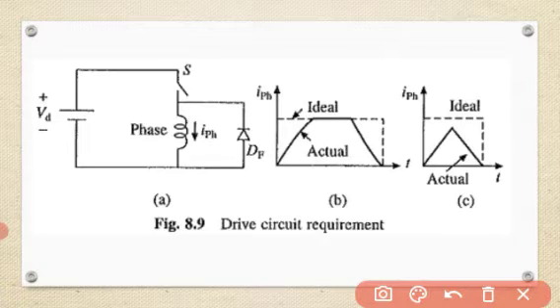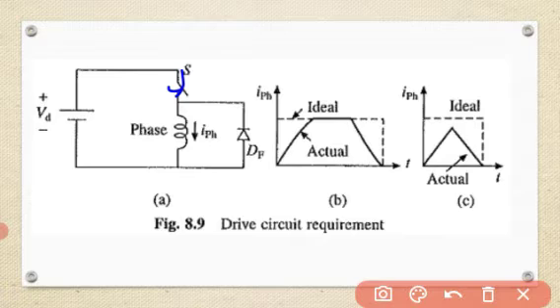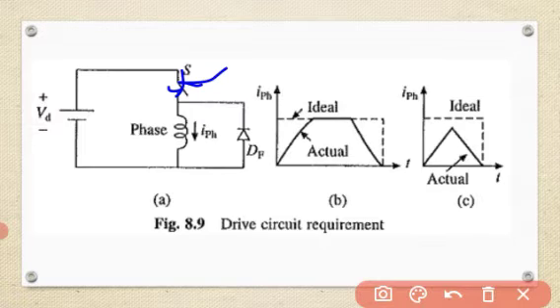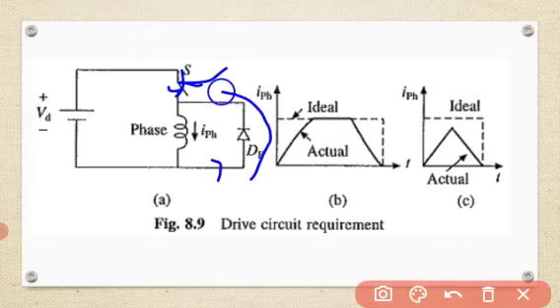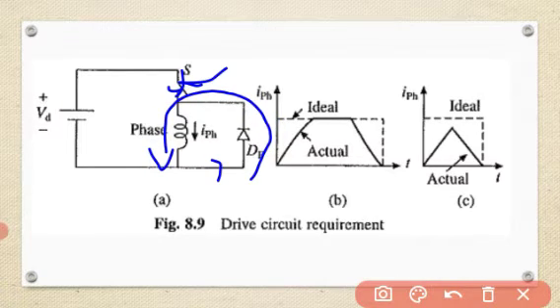When the phase is to be de-energized, the switch is turned off, which transfers the current to the freewheeling diode. The current flows through the freewheeling diode and drops to zero again at the rate decided by the time constant of the phase winding.